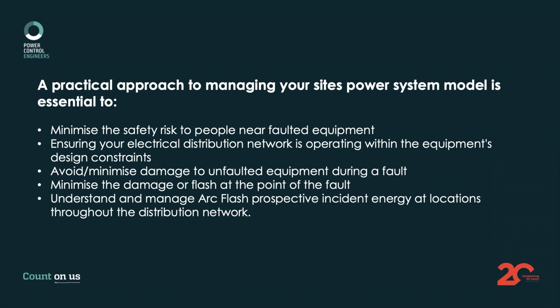Properly managing your site's power system model is essential to minimise the safety risk to people near faulted equipment, ensuring your electrical distribution network is operating within the equipment's design constraints, avoiding damage to unfaulted equipment, minimising damage at the point of the fault, understanding and managing arc flash prospective incident energy levels at locations throughout the distribution network, and of course maximising reliability.